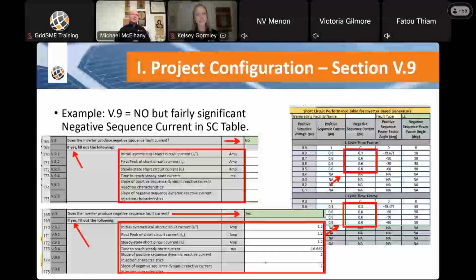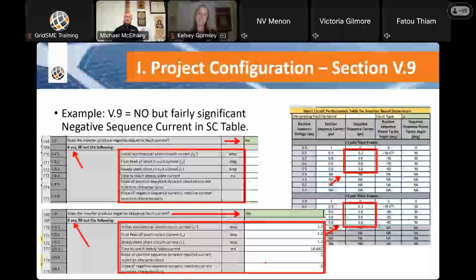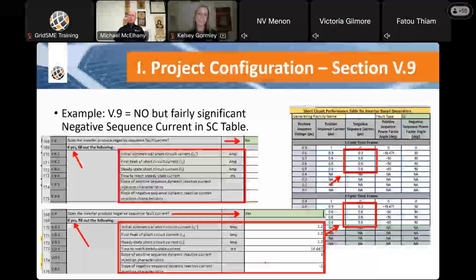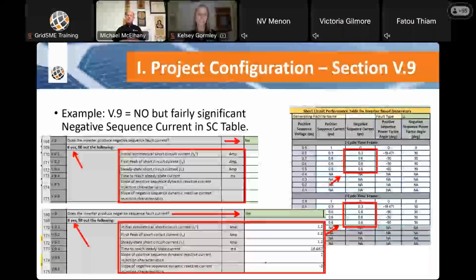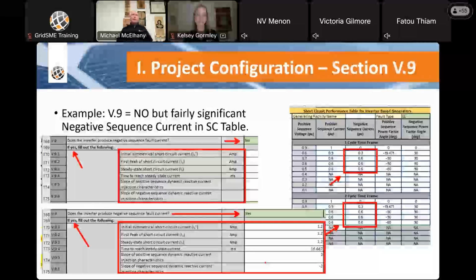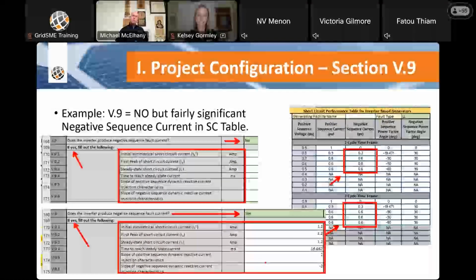And this is actually a Tesla inverter. We've gone back to Tesla and they confirmed that they do produce the negative sequence current. You should never have negative sequence current on a balanced three-phase fault.